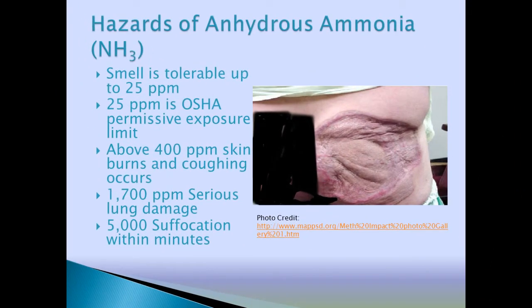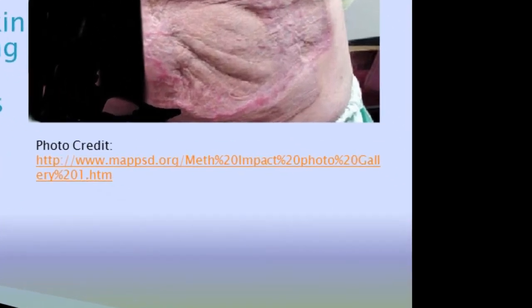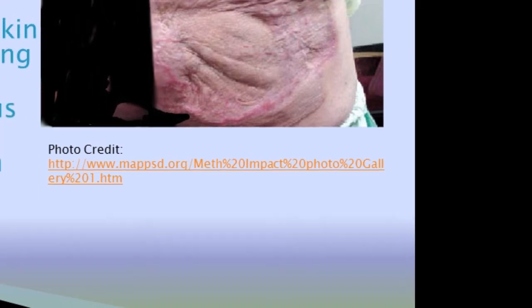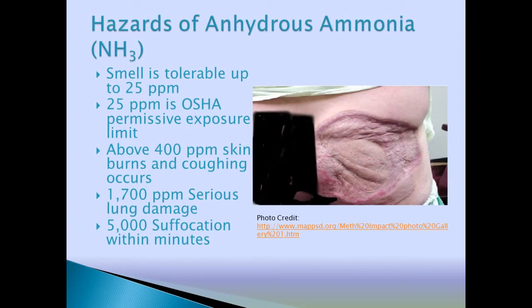You'll get used to the new GHS labelings as you see more of them. At the bottom of the picture there's a photo credit for where the picture is coming from. This is the damage that anhydrous ammonia can have on skin contact. Some of the hazards: the smell up to 25 parts per million is tolerable. 25 ppm is OSHA's Permissible Exposure Limit (PEL) for anhydrous ammonia. Above 400 ppm, the skin burns, your lungs are burning, you're coughing.